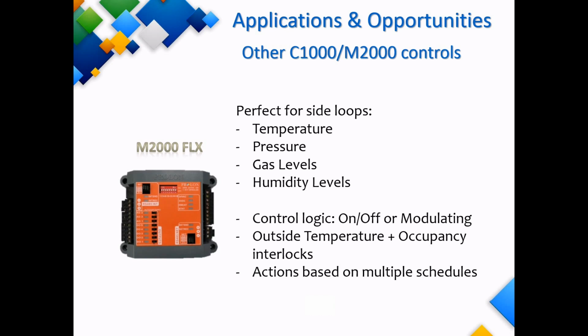The inputs can be configured to read temperature, pressure, gas levels, humidity levels, or can be a simple dry contact for status. Each input can then be linked to an output, and we can configure the set point and other parameters to determine when the output turns on and off. The controller has both digital and analog outputs, so it can be simply used for on-off operation, or you can modulate a signal. It is ideal for monitoring temperatures.